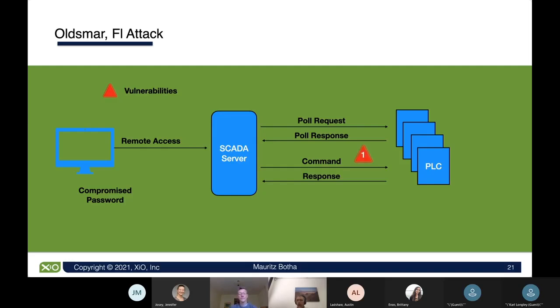Right there is one of the big vulnerabilities that we see. This command-response is master-slave, so the PLC typically doesn't have any way to verify the origin of the information. In some cases, it may be something as simple as a very simple password or an IP address, but even that can be spoofed. So anybody that can get access to that communication network can exploit any vulnerability.